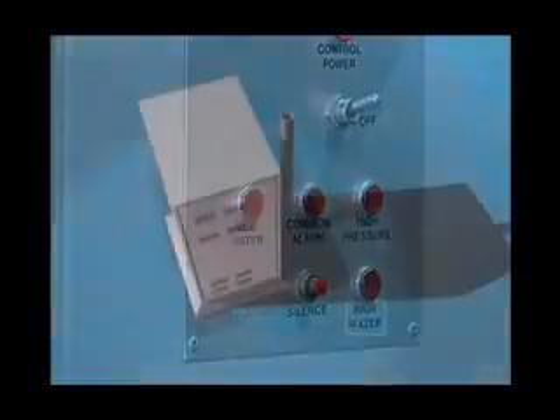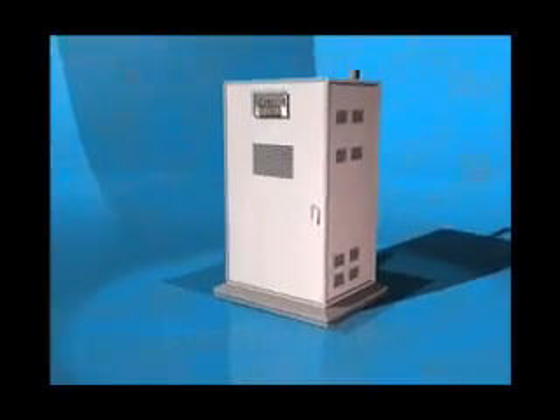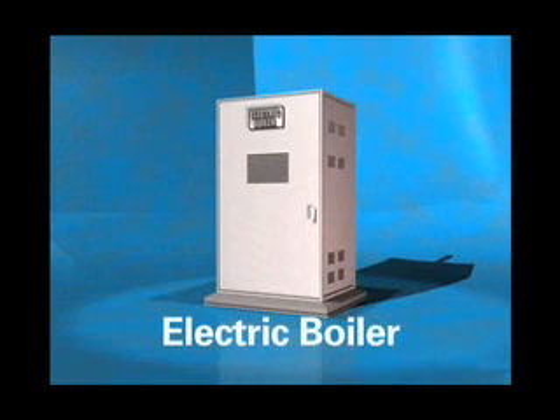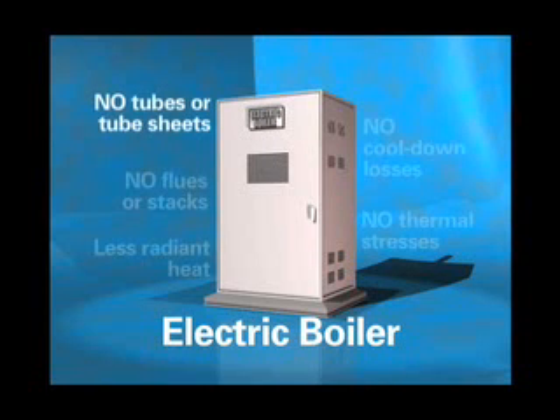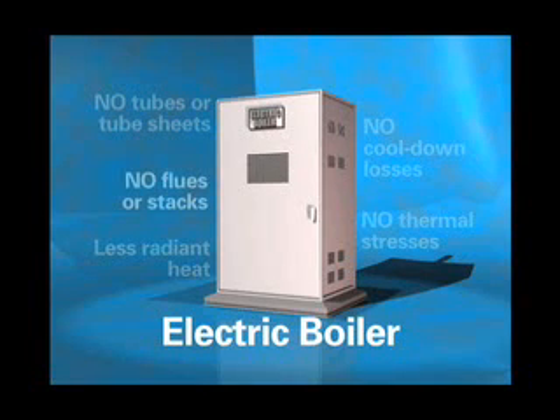Yeah, but electric heating elements use a lot of electricity. Well, think of it this way. They use energy more efficiently. Heat goes directly into the water instead of heating up a ton of metal first. And there's no buildup of minerals and corrosion on tubing to lower efficiency. With conventional boilers, about 17% or more of the energy you pay for goes up the flue or radiates into the boiler room. That's why it's always so hot in there.